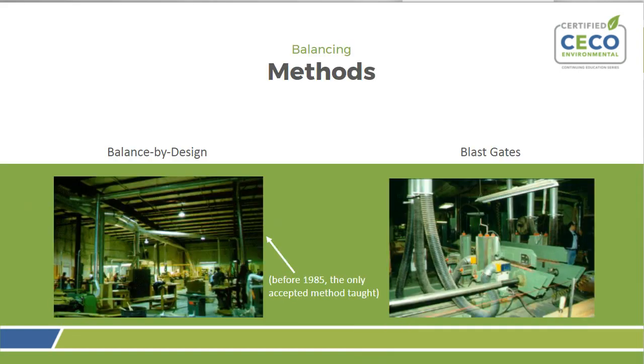Balancing. Whenever you do a system, you have to balance it. If you don't balance it, the fan will balance it for you, and the effects are not always going to be good. You can balance by design. This note says before 85 it was the only accepted method that was taught. Balance by design is problematic in that you have to manipulate duct diameters and elbow configurations to try and match static pressure. When you do that, you can create high pressures and high velocities in the duct, and it'll wear out sooner. So your choice, and when you do a balance by design, what gets installed is not always exactly what you have on paper, so it's not going to balance for you. It'll steal air from the leg that has the higher static pressure and overload a line that has a lower static pressure. That's your junction point.